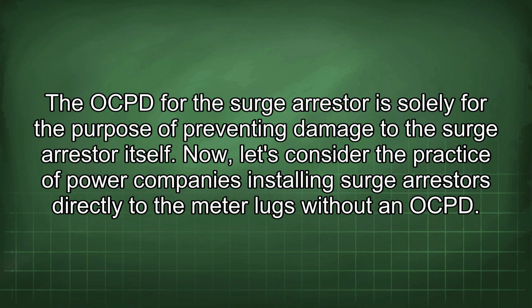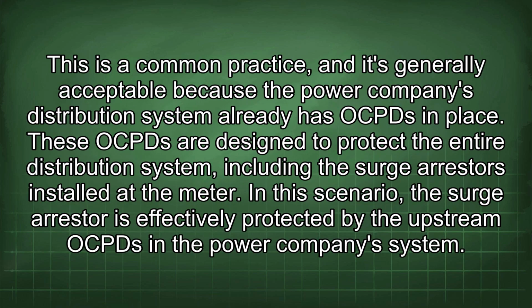Now let's consider the practice of power companies installing surge arrestors directly to the meter lugs without an OCPD. This is a common practice, and it's generally acceptable because the power company's distribution system already has OCPDs in place. These OCPDs are designed to protect the entire distribution system, including the surge arrestors installed at the meter. In this scenario, the surge arrestor is effectively protected by the upstream OCPDs in the power company's system.